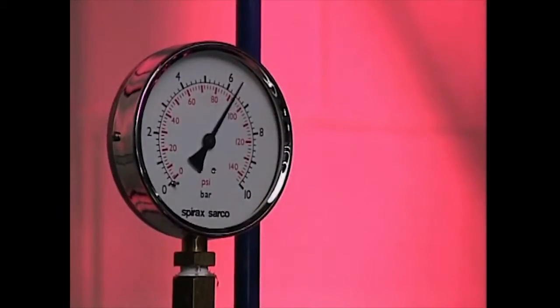Falling pressure has a major effect inside the boiler. Watch as the steam demand is temporarily increased but within the boiler's maximum output capability. The bubbling water surface begins to rise with surprising speed and within a few seconds the level is so high that water and foam are being drawn into the steam takeoff.